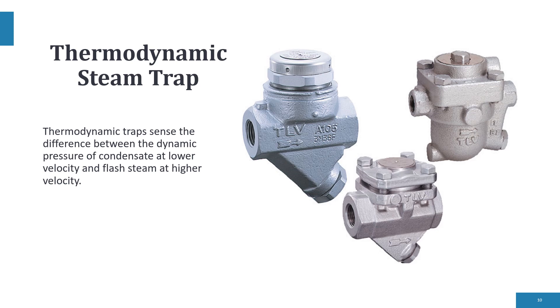Next are thermodynamic traps. These sense the difference between the dynamic pressure of condensate at lower velocity and flash steam at higher velocity. This is the most common steam trap used in commercial and industrial plants due to its compact, simple, lightweight design and large condensate capacity for its size.